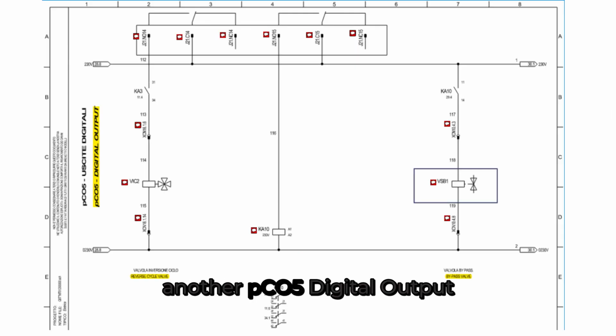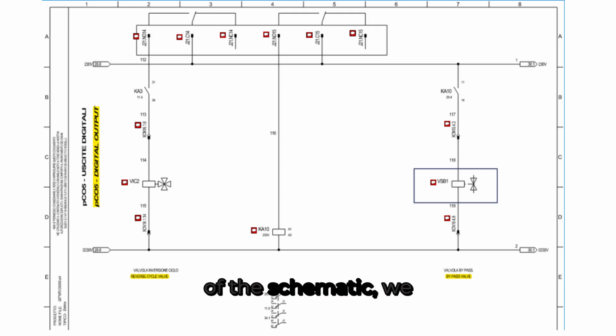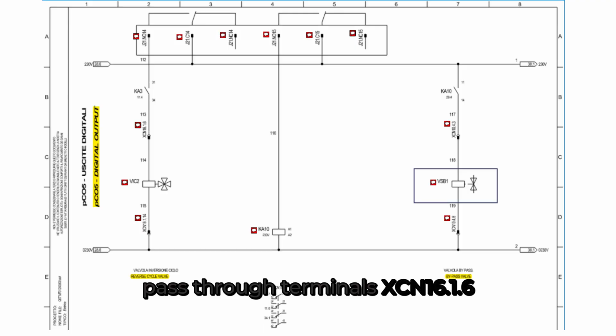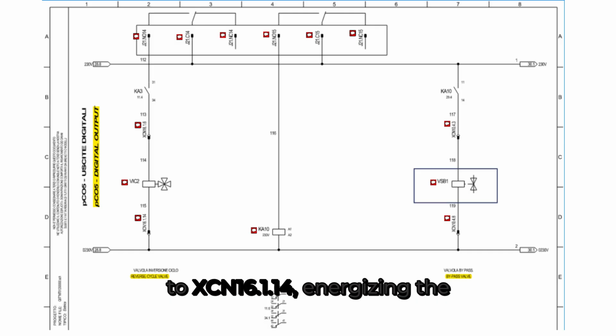We're now looking at another PCO5 digital output page. On the left-hand side of the schematic, we see the control for the reverse cycle valve VIC2, which manages the refrigerant flow direction to switch the unit between heating and cooling modes for circuit 2. The 230-volt supply feeds a set of relay outputs at the J21 terminal block. From there, the circuit continues through KA3, a relay coil for the high-pressure switch that acts as the interface between the relay output and the reversing valve coil. When KA3 is energized, it closes its contacts between terminals 31 and 34, allowing voltage to pass through terminals XCN 16.1.6 to XCN 16.1.14, energizing the VIC2 reversing valve coil.